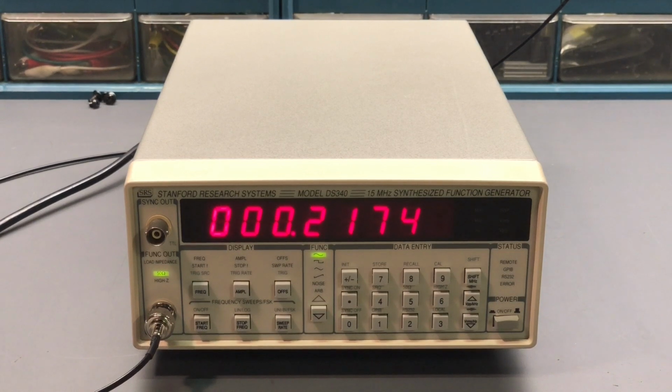If you mess up the cal bytes and really need to start over, there is a procedure to reset the cal bytes, clear out the RAM, and it will reload all of the cal bytes from ROM again, and you can start all over. So really, you can get back to a starting point if you really mess up, particularly if you make adjustments to the wrong cal byte or lose track of where you're at or something like that. So it is a way that you can restore the instrument, basically.